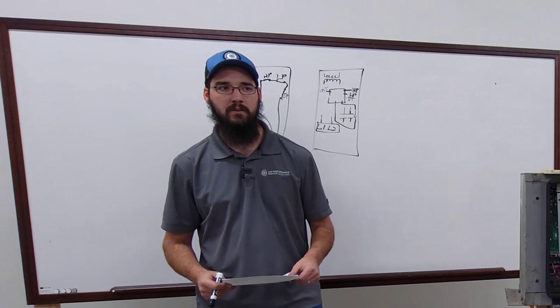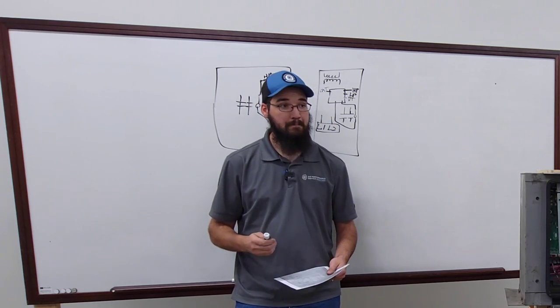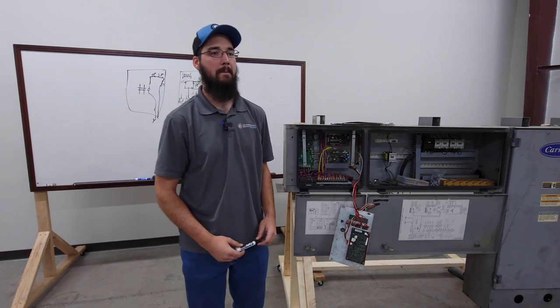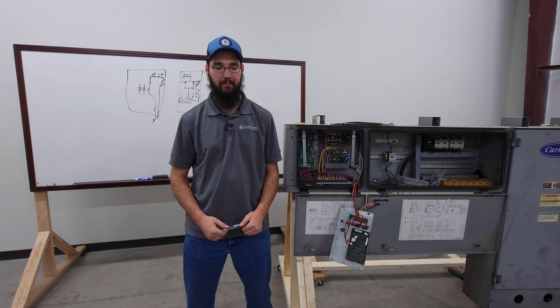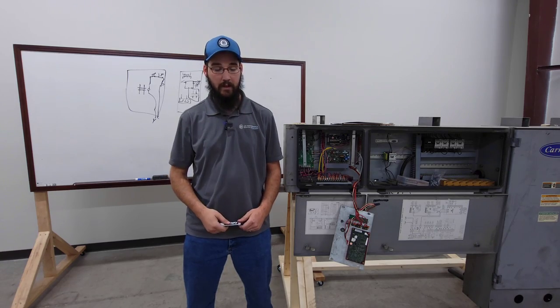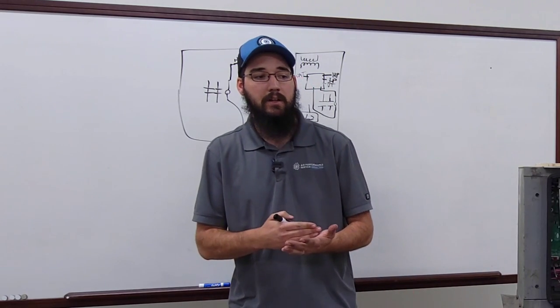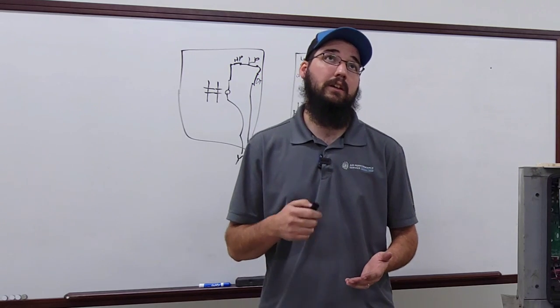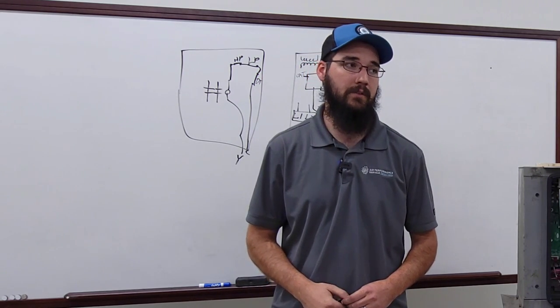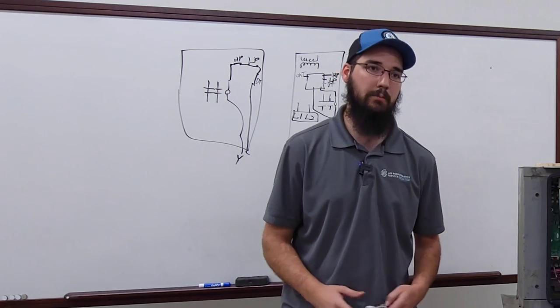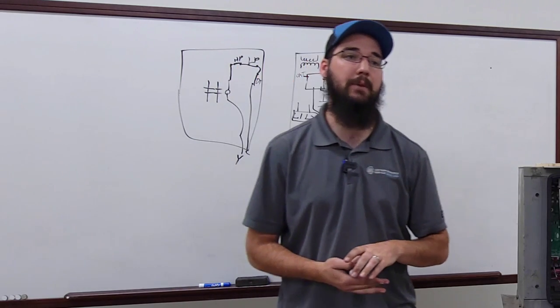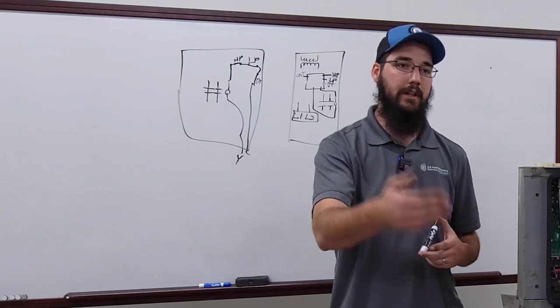Those are lessons you hopefully won't have to learn if you try to apply these things and adjust your mind to this new concept of troubleshooting. A question came up about controls that put out DC — are there other controls that only run on DC? Yes. A lot of automation systems will have DC control, but an SCR heater is a prime example. That's something we run into frequently that still gives everybody trouble. Those are DC input controllers.